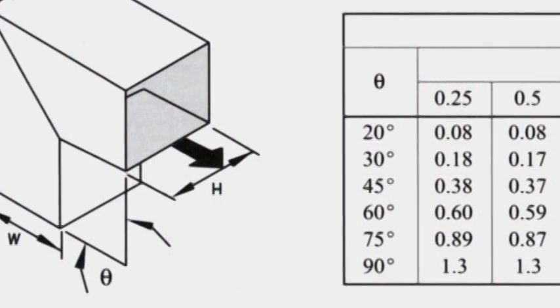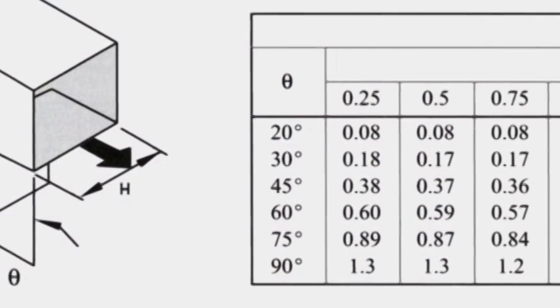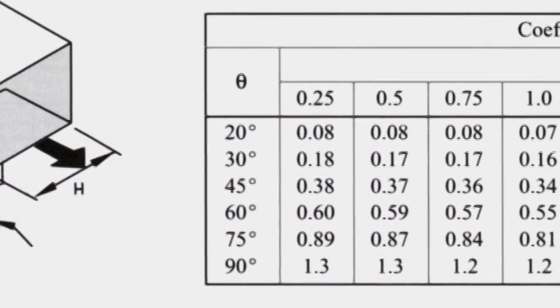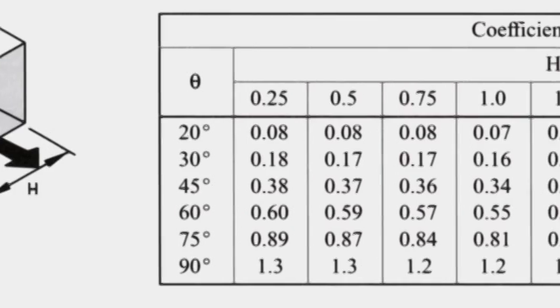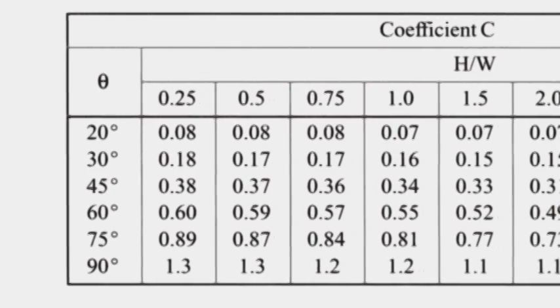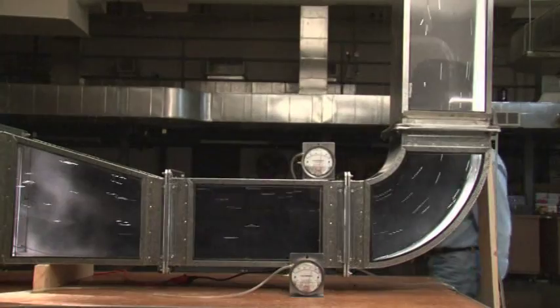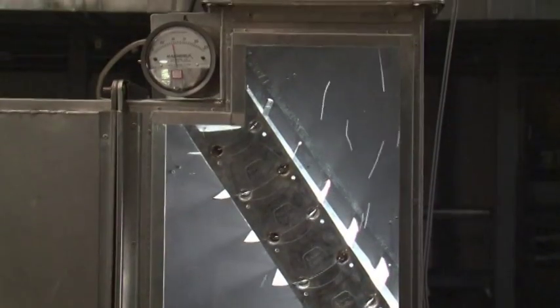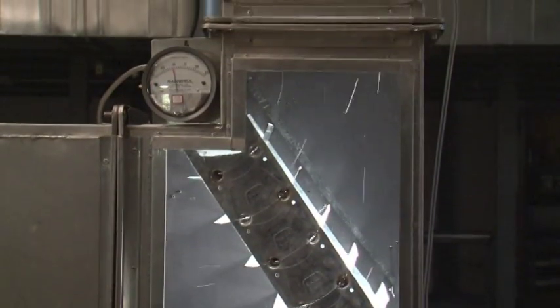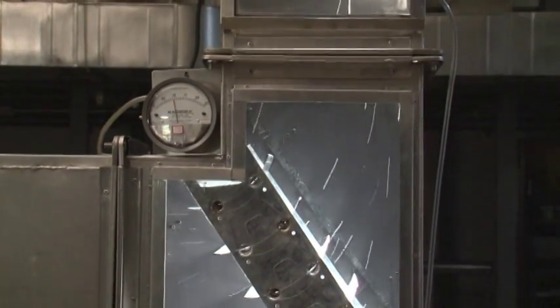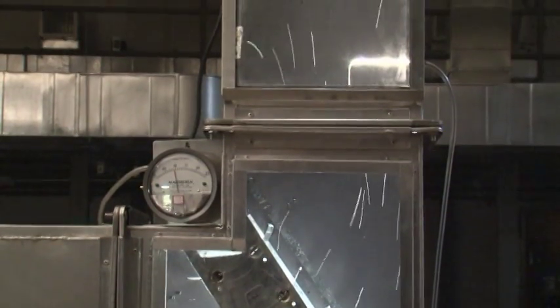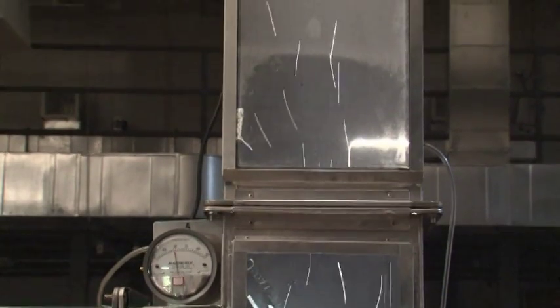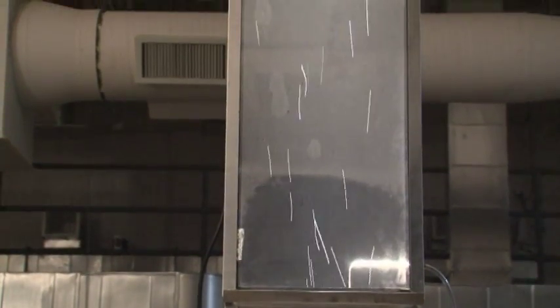This table shows the loss coefficient, which is a part of the pressure loss function formula. However, air velocity plays a major factor in duct pressure loss, and the slower the air velocity, the lower the potential energy savings are to offset the higher construction costs of these types of fittings.